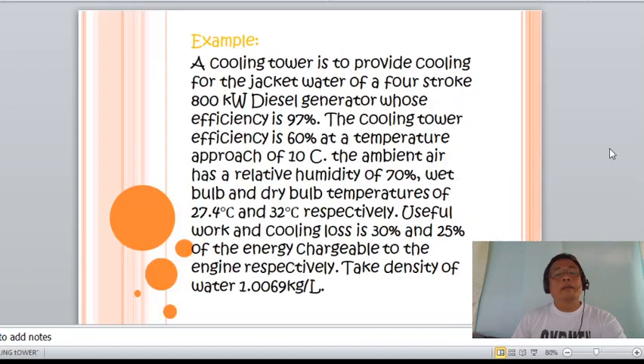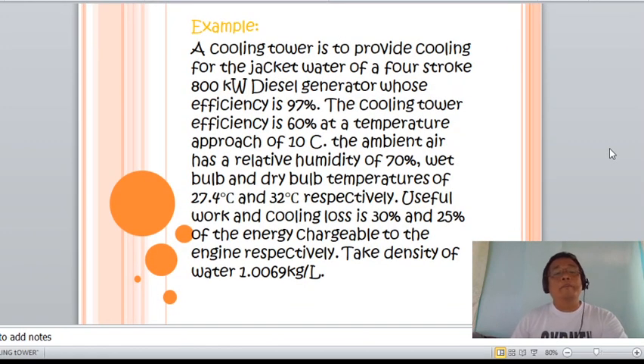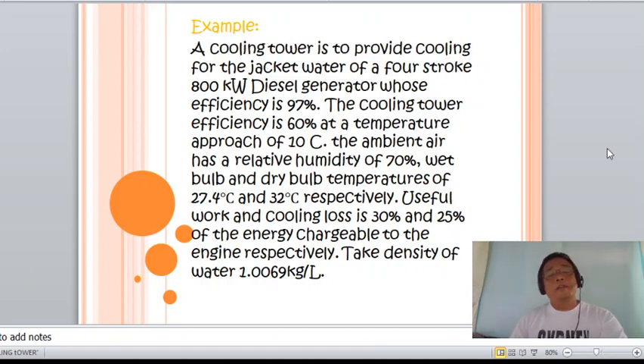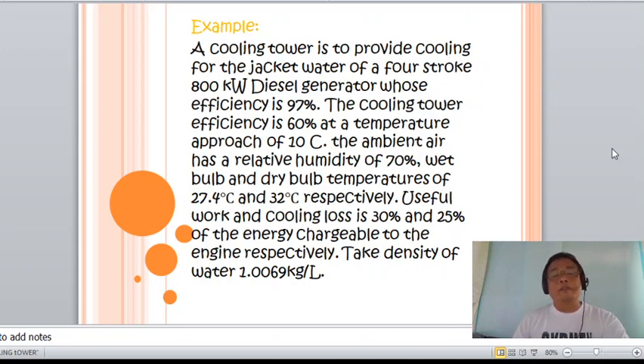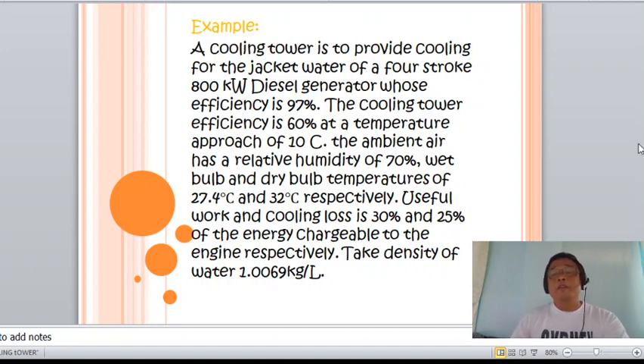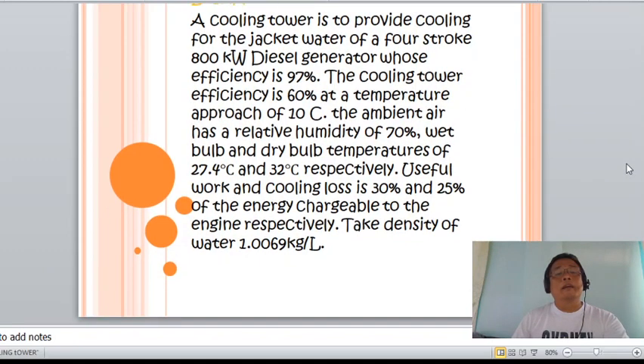A cooling tower is to provide cooling for jacket water for a four-stroke 800-kilowatt diesel generator. The generator efficiency is 97 percent, the cooling tower efficiency is 60 percent at a temperature approach of 10°C. The ambient air has a relative humidity of 70 percent with wet bulb and dry bulb temperatures of 27.4 and 32 degrees Celsius respectively. Useful work and cooling loss are 30 percent and 25 percent of the energy chargeable to the engine respectively. Take the density of water as 1.0069 kg/L.